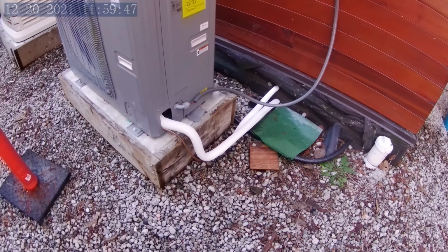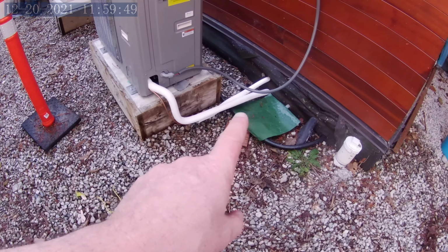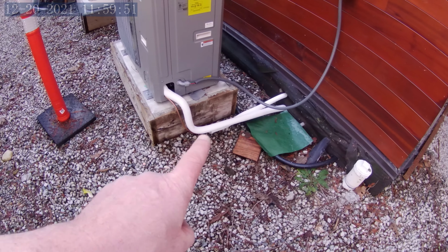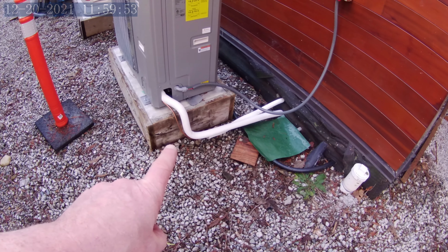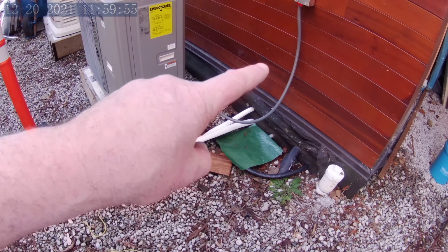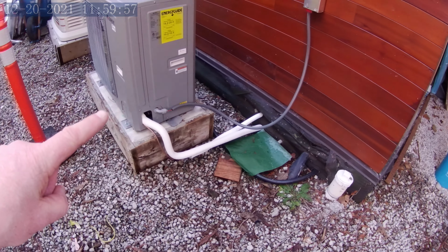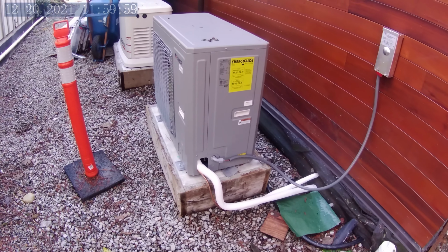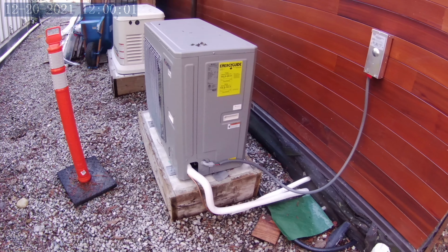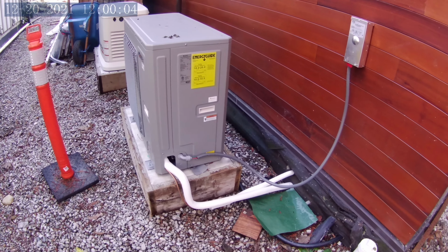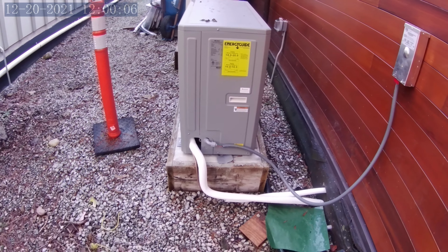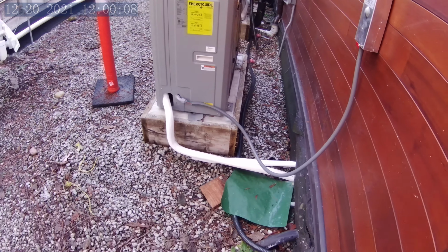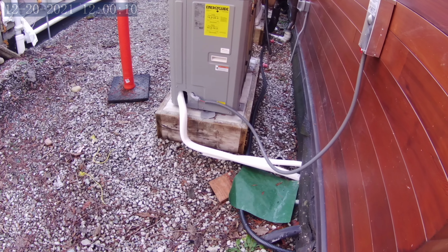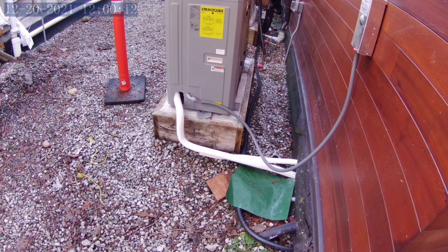So what I screwed up is I wasn't thinking this will actually be below the concrete level of the poured pad, and what I need to do is loop it up and over so that it has an anti-drain loop in it, and that's something to do with the refrigerant. So I'm still in the process of working that out, and I'll probably have to replace the 3/4 line because I had already cut it.